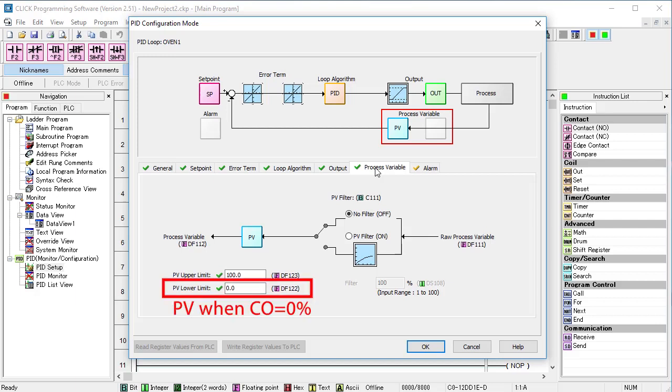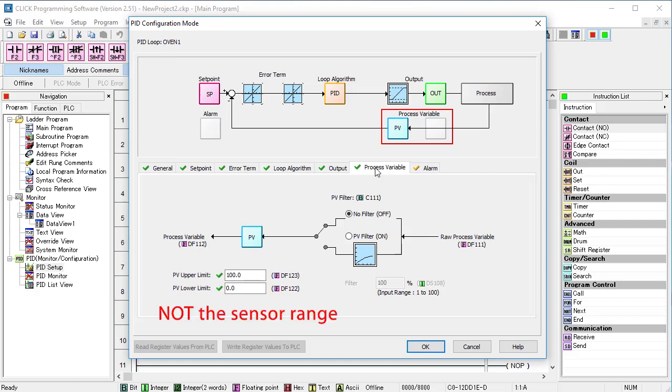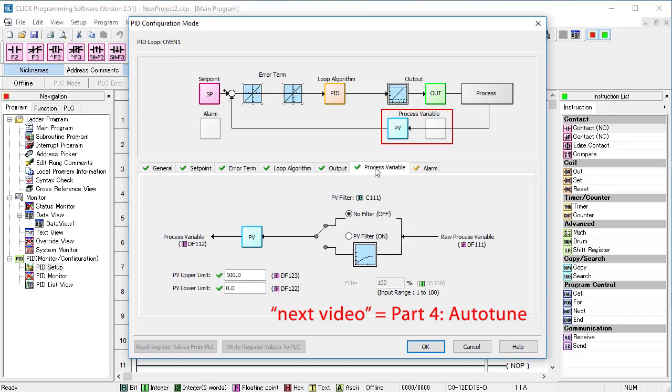This one is the process variable level when the control output is 0. And this one is the process variable level when the control output is 100%. Exactly what it says – the min and max process variable. PID needs to know this so it can scale things correctly and keep things in engineering units. Just remember, this is not the 0-300 degree range of our sensor, it's the range of the process variable which we are going to measure in the next video.